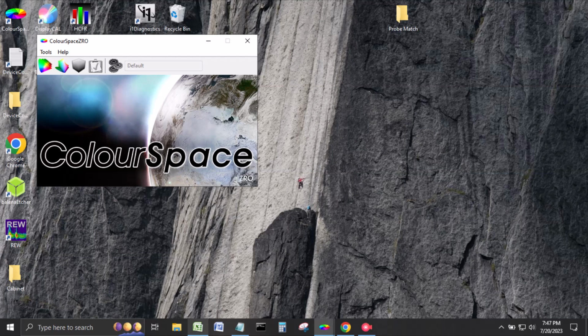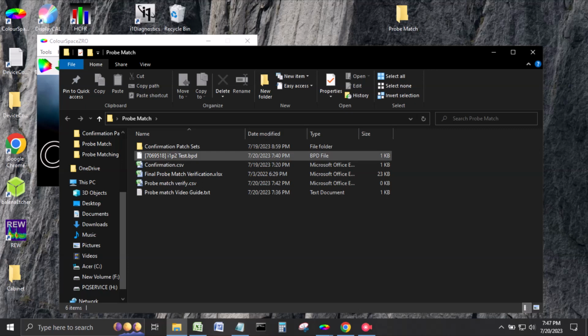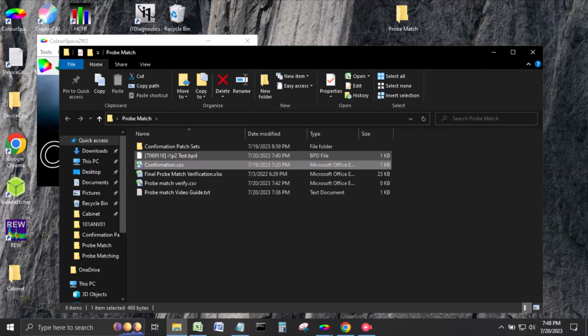Always delete the files once you verify that your probe match is accurate. And what do I mean by that? I mean the confirmation and the .bpd file. Always create new iterations of these files every time you do the verification. Don't write over them or rename them. It will just cause problems for you. So my best advice is to just delete these once you're done with them. And then when you go to probe match verify next time, start with a clean slate of files so that it just makes it easier. What happens in this CSV file is if you override it for whatever reason, it will just keep adding data below the existing data set. So it gets a little confusing. So your best bet is just delete these and start with fresh files every time. But that's pretty much it.